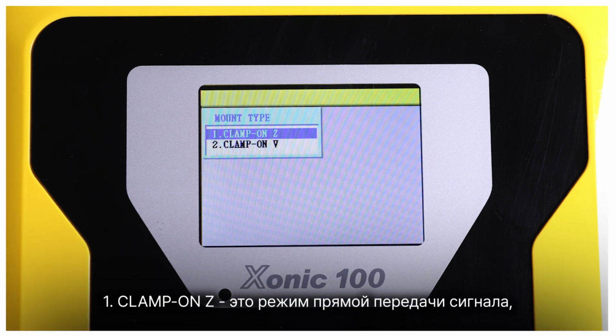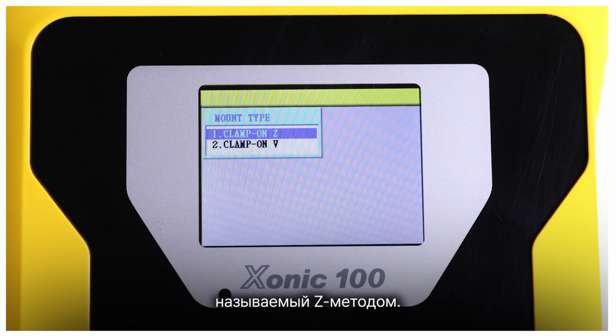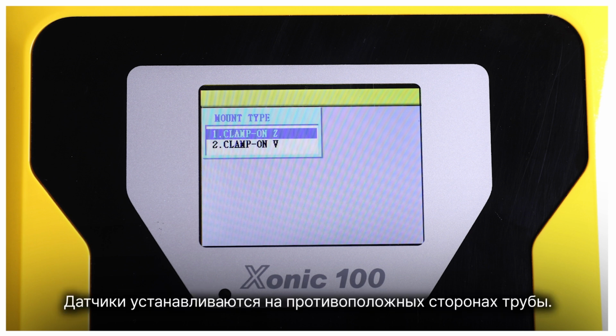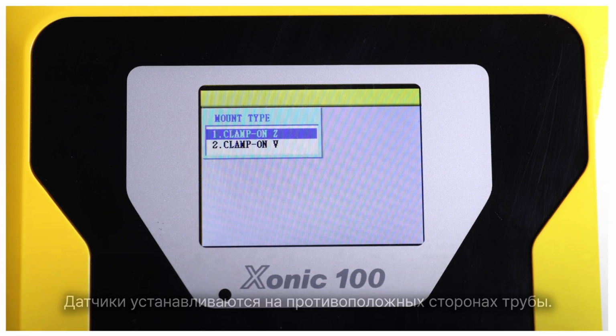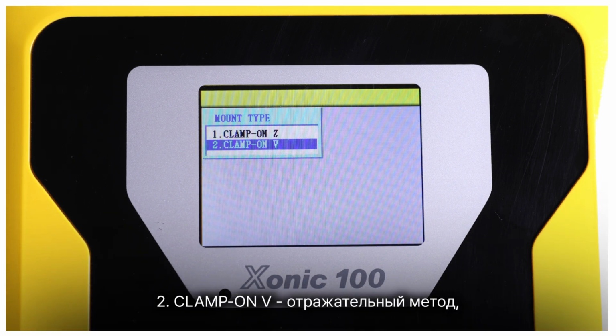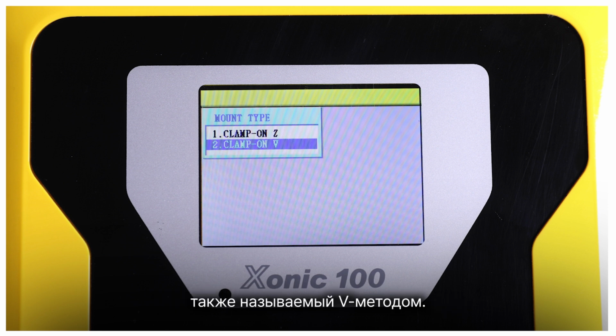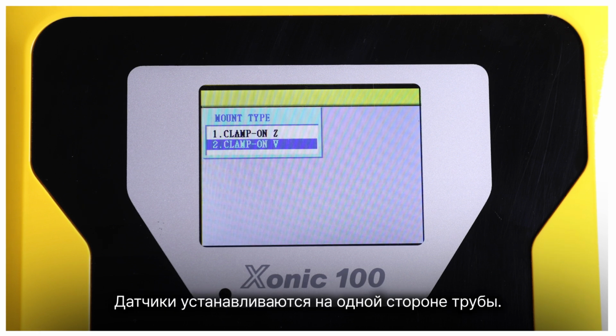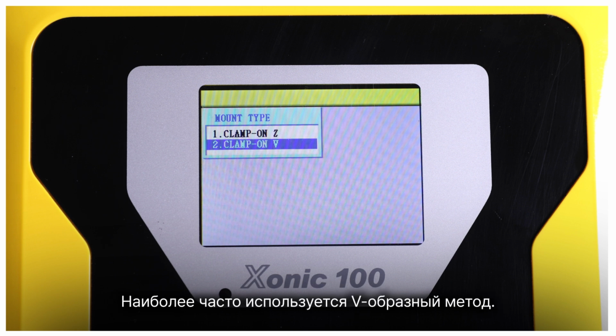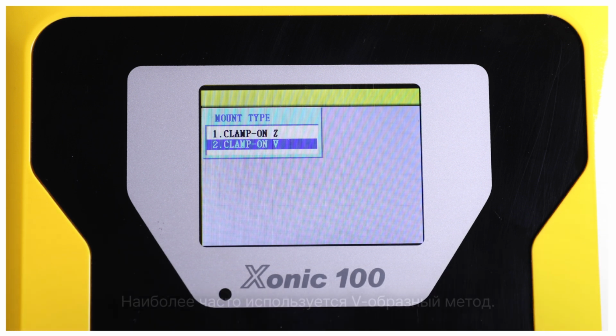Clamp-on Z is the direct transmission mode called the Z method. The transducers are mounted on opposite sides of the pipe. 2. Clamp-on V is the reflective method, also called the V method. The transducers are mounted on the same side of the pipe. The V method is the most used method.